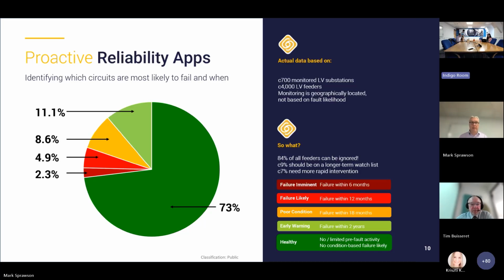However, there are a smaller number of circuits shown by the red and the deep red, 2.3 and 4.9% there. So you're looking at around about 7.5% of the circuits which are expected to fail within the next year. We classify these using the application into failure imminent and failure likely. These algorithms have been trialed and tested over a number of years, and basically circuits have been allowed to run to failure to evaluate the accuracy of these algorithms. What we now find is that anything put into that failure imminent category, about 1/3 of those circuits fail within 1 month, and around about 2/3 fail within 6 months.